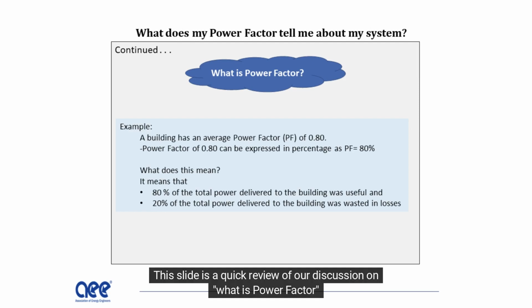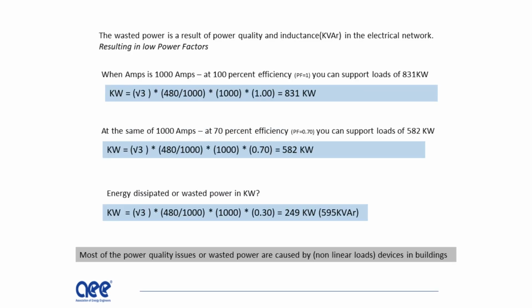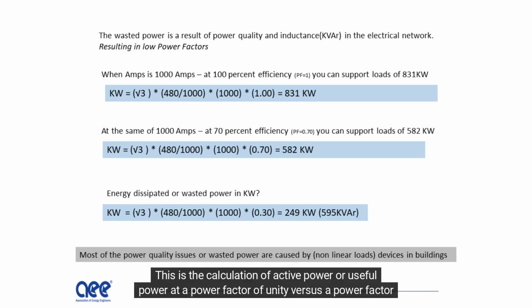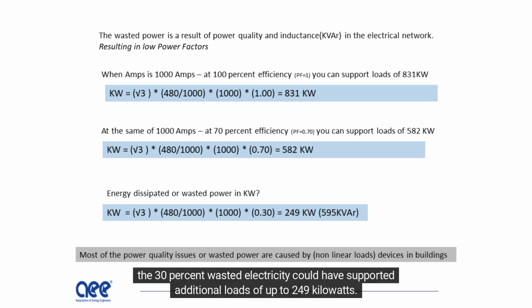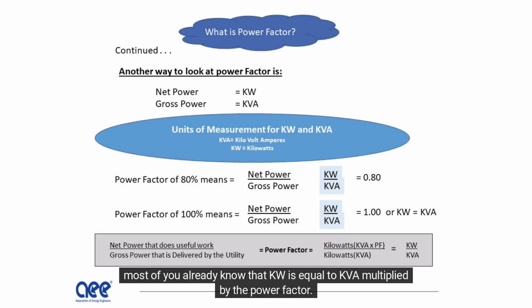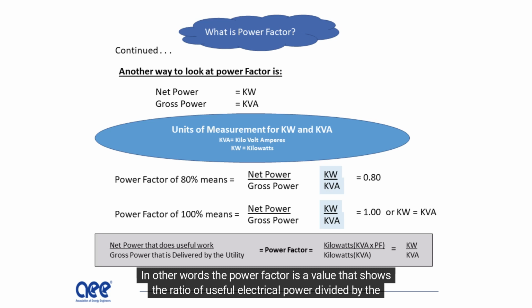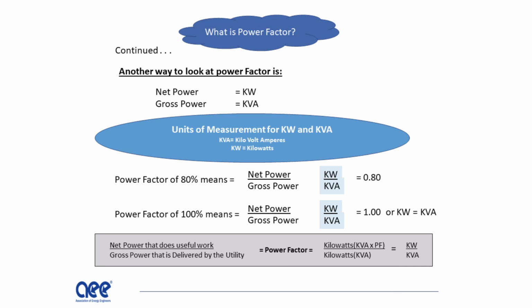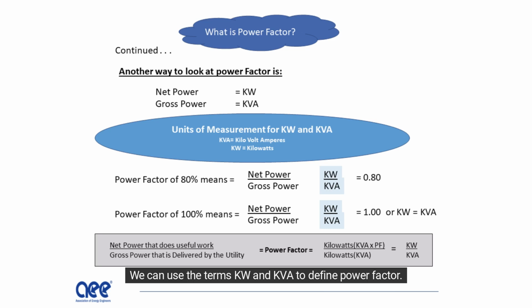This slide is a quick review of our discussion on what is power factor. This is the calculation of active power or useful power at a power factor of unity versus a power factor of 70%. The 30% wasted electricity could have supported additional loads of up to 249 kilowatts. Most of you already know that kW is equal to kVA multiplied by the power factor. In other words, the power factor is a value that shows the ratio of useful electrical power divided by the gross electrical power. Let us state it in another way. The active power divided by the apparent power is the ratio called the power factor. We can use the terms kW and kVA to define power factor. kW divided by kVA is equal to the power factor of the building.